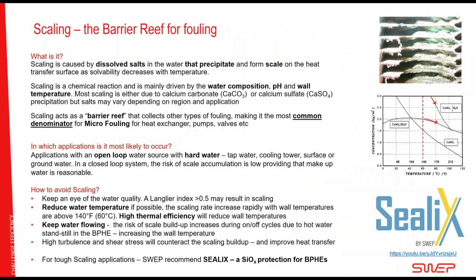So the last of the big three, scaling, the barrier reef of fouling. Unfortunately, not a nice one. So what is scaling? Scaling is salts. So it's not a suspended thing anymore. It's actually dissolved in the water. So it comes in. You cannot stop it by any filter or mechanical filter, and then it will precipitate and form scale if the salt is the type where the solubility decreases with temperature. Those are typically carbonates and sulfates. And the main important things here are the water composition, the pH, and the wall temperature. And the only thing that we can really do something about is the wall temperature. So that's what we'll focus on.